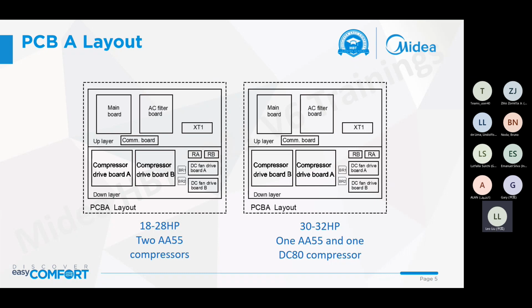It's a layout. We have two layouts. The first one is for two compressors and two fan motors. The left one is for 18 horsepower to 28 horsepower. These models have two small volume compressors, so we can see two compressor drive boards, one main PCB, one AC filter board, and two DC fan drive boards.